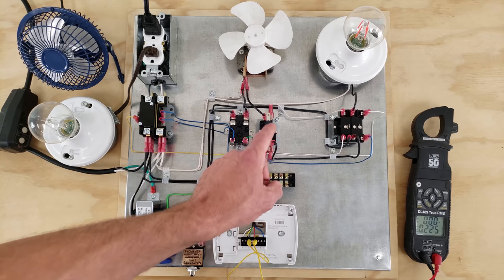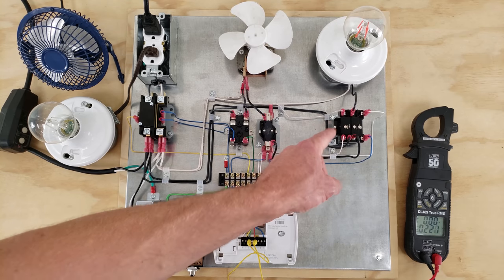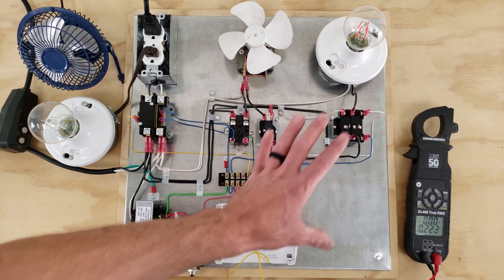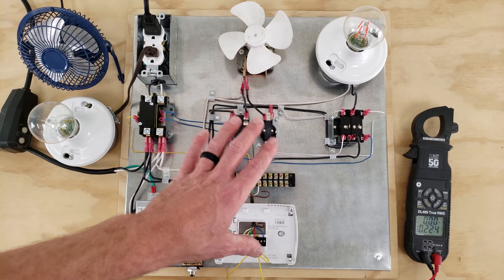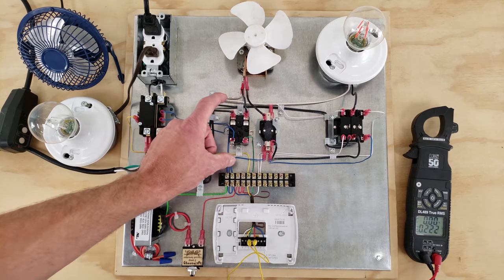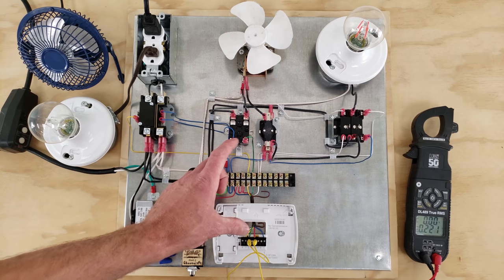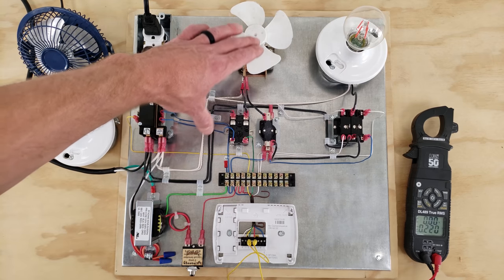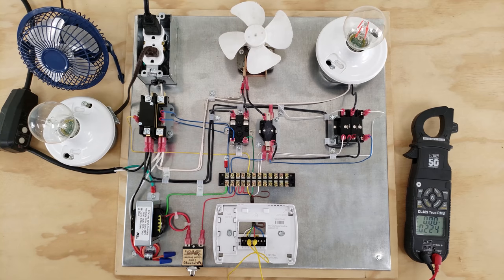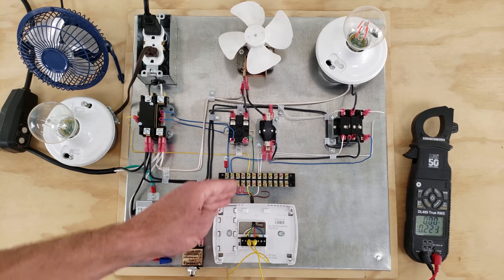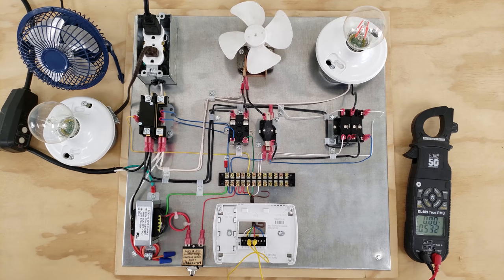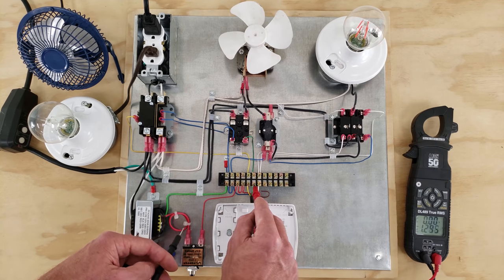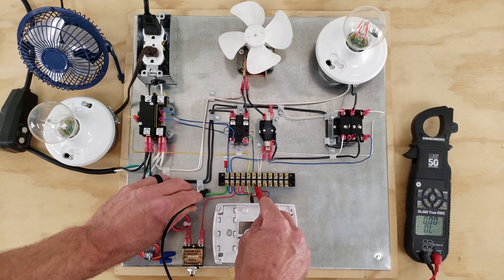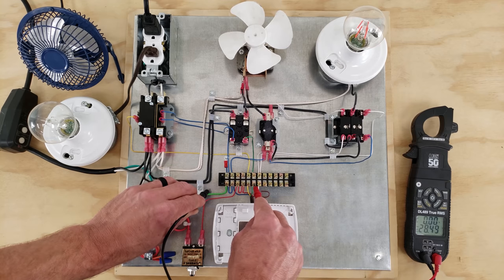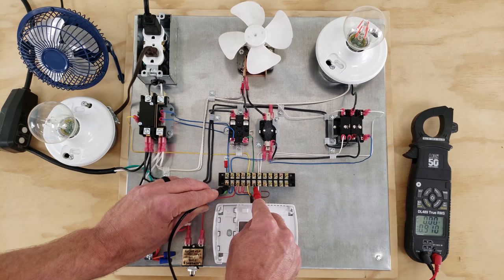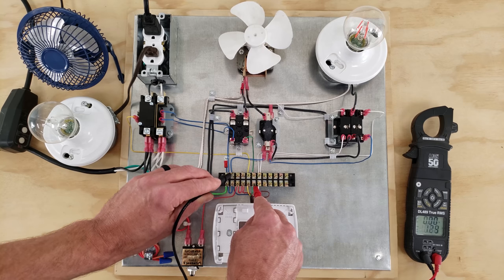And since we know that our sequencer and our general purpose fan relay are used during heating in this wiring right here, we know that our issue is either at our fan relay, or it's our low voltage to the fan relay, or it's the high voltage going to the fan. And so what we want to do is start from here and move this way. So what we'll first do is measure from our G to our ground, and we do have 29 volts. Now let's just verify that we do also, yep, so 29 volts.